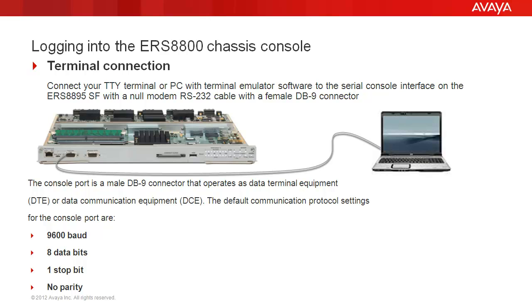The console port on the card is a male DB9 connector and operates in data terminal equipment or data communication equipment mode. The default COM settings are 9600 baud, 8 data bits, 1 stop bit, and no parity.